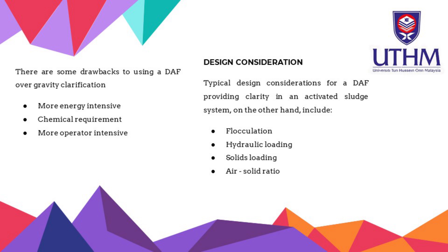For the design consideration, some fundamental design issues exist for DAF clarifying of biological solids. These are considerably dependent on the type of biological materials being cleared and the necessary effluent quality. For example, the solid loading of a DAF treating anaerobic effluent may differ somewhat from that on an activated sludge system. The typical design considerations for DAF include flocculation, hydraulic loading, solid loading, and air to solid ratio.